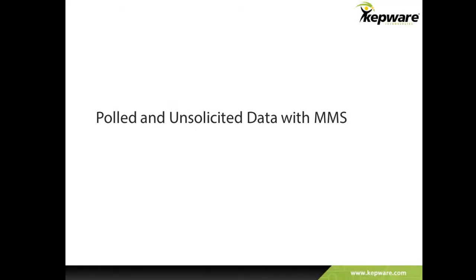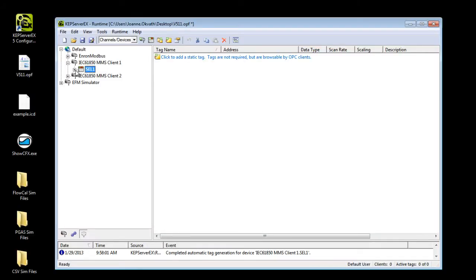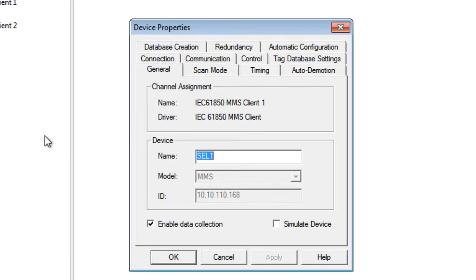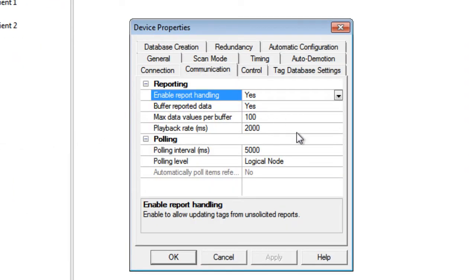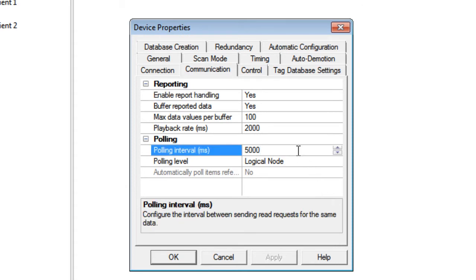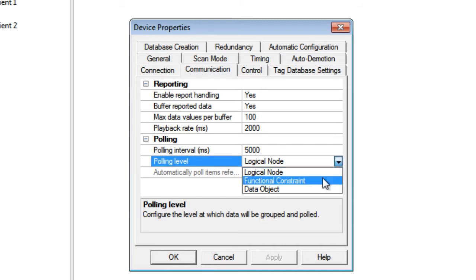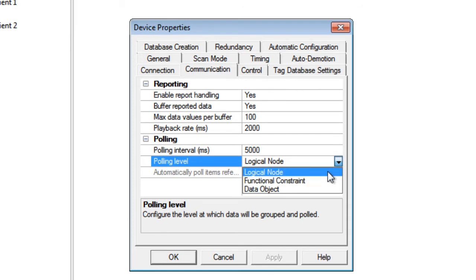Now, let's move on to getting data from the device using polled and unsolicited methods with the MMS. Users may easily read and write to the device using the IEC61850 MMS client. In the device properties communication tab, data may be set to be polled at a rate, for example once every 5 seconds. For optimal communications, users may poll data for an entire logical node at once, where one solicited request would include all the data relevant to the node, for example the protection node of a circuit breaker. Otherwise, options for polling data at the functional constraint or data object level give users greater flexibility in bandwidth or memory limited applications.